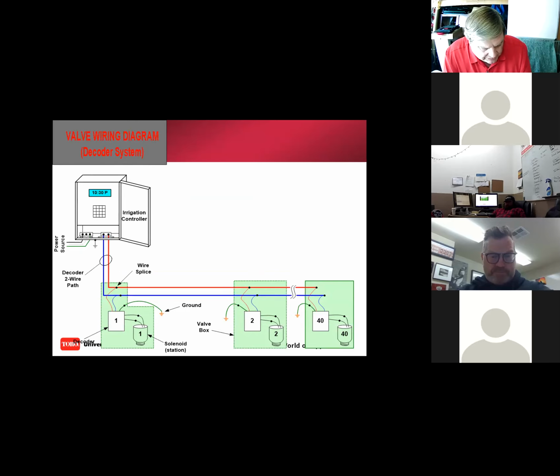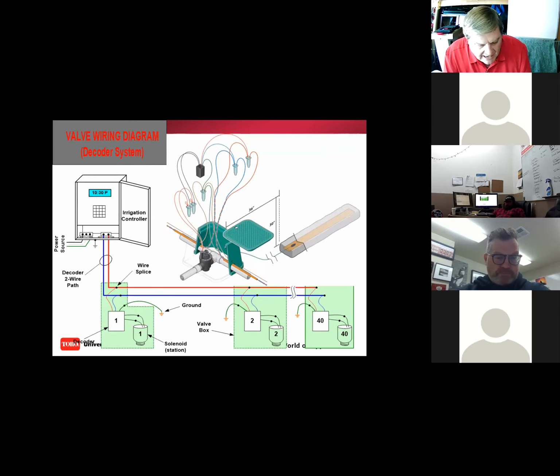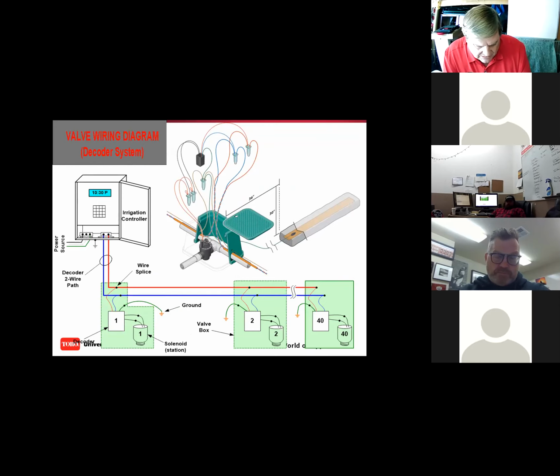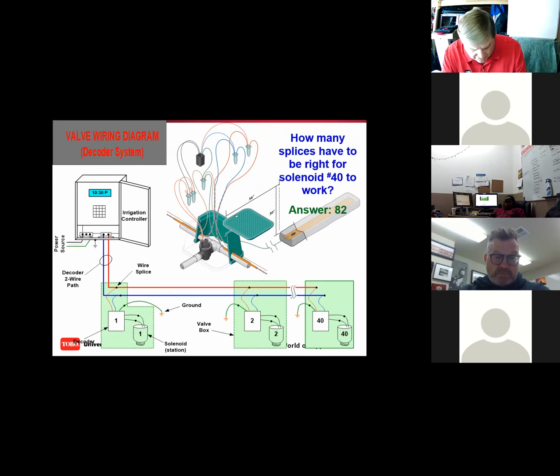Now you've got to look at the different wire connections along that two-wire path. Getting to that 40th zone, how many connections do we need at this point? The bare minimum. You need two connections for each of the decoders. You need two connections for the valve. So we're looking at a minimum of 82 in this scenario. A lot more connections and a lot more opportunity for trouble.